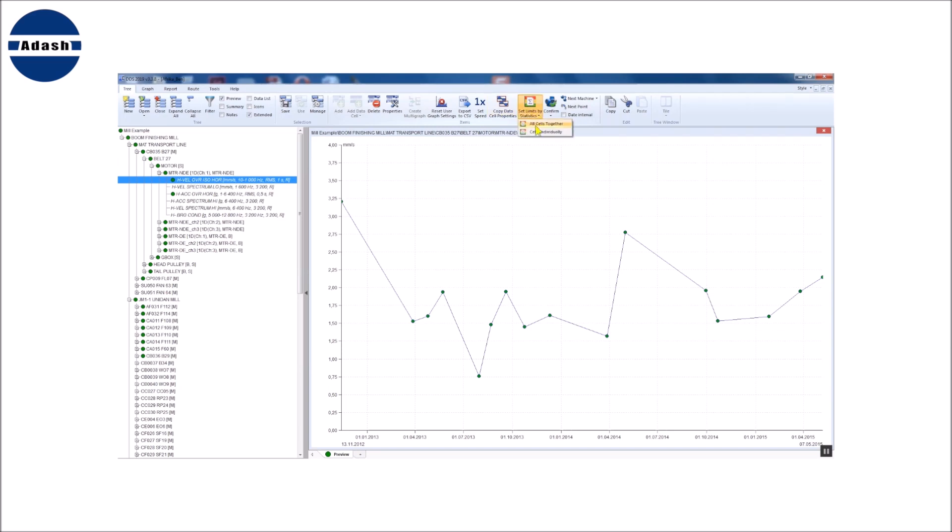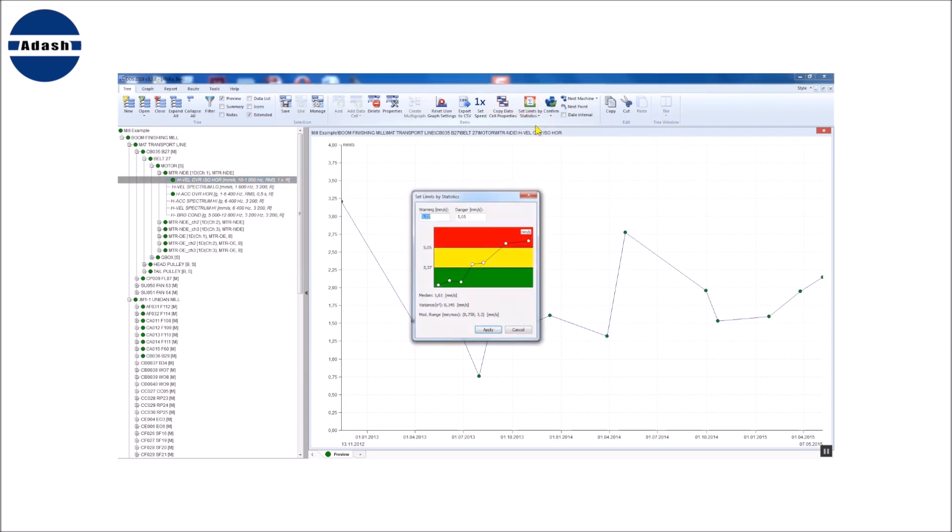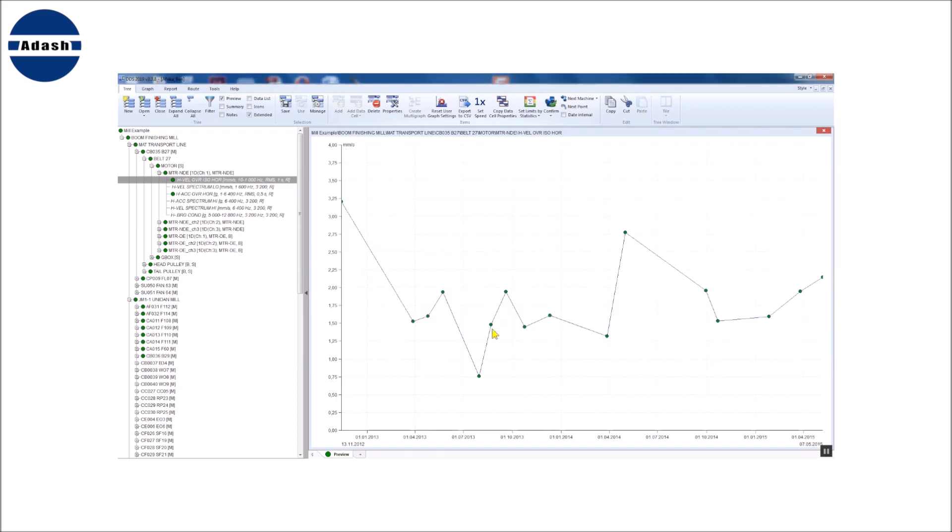I will explain these two options later. The function firstly analyzes all vibration values of selected data cell. Then it uses the statistical approach and gives back the limit values. I push apply and limits will be written to data cell.